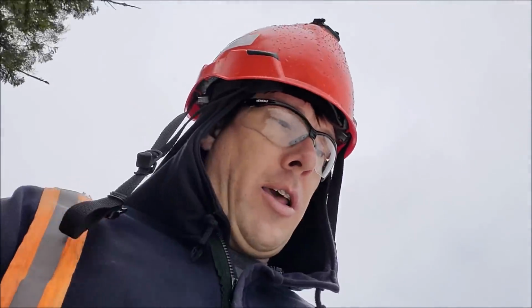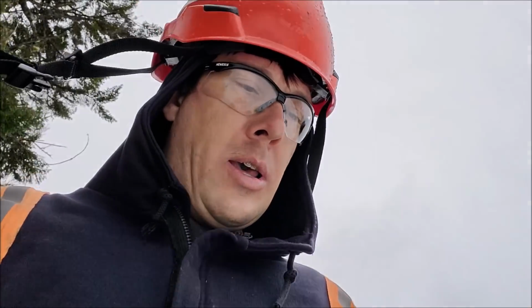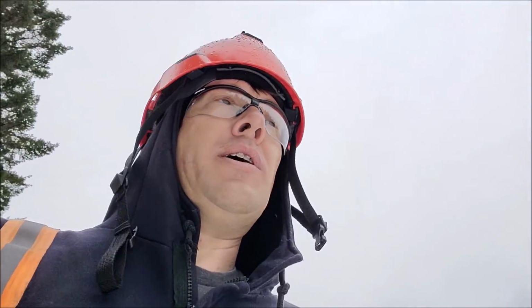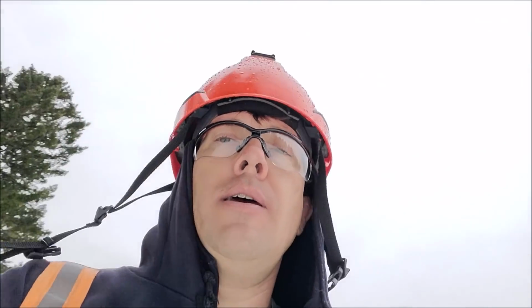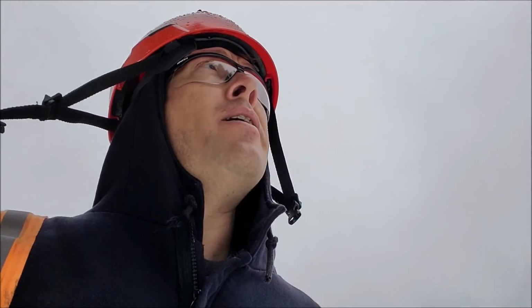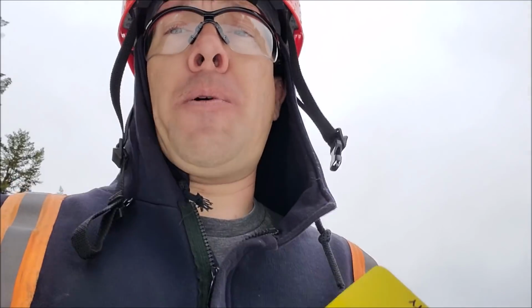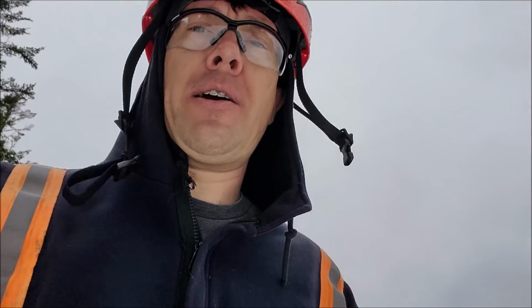So we're going to be installing what we call an abnormal conditions tag on the switch. In our company, no one is to operate any switches without going through our switching authority, our dispatcher. So on the system at dispatch, they have it tagged saying do not operate this device because there's a bad underground cable.